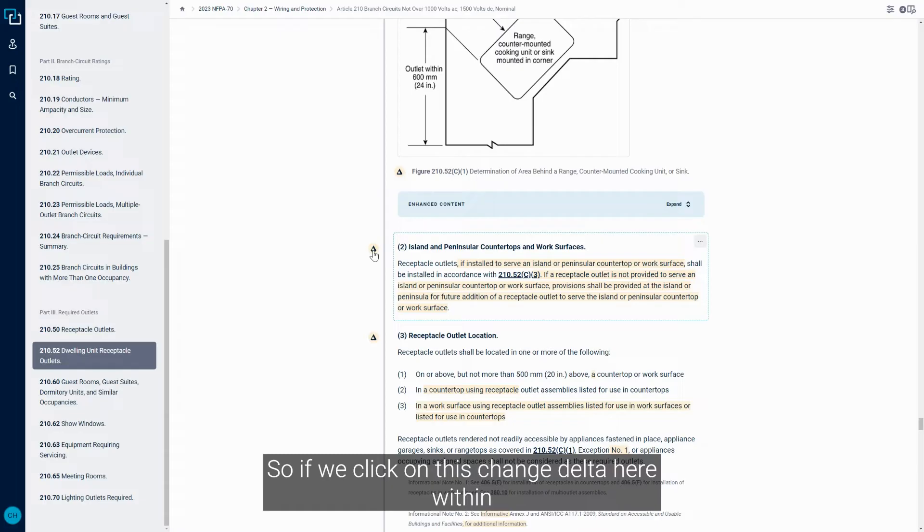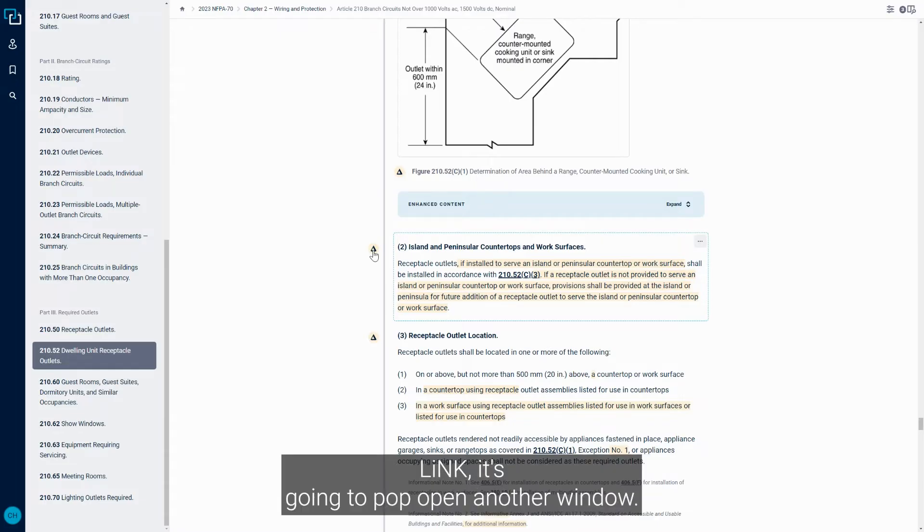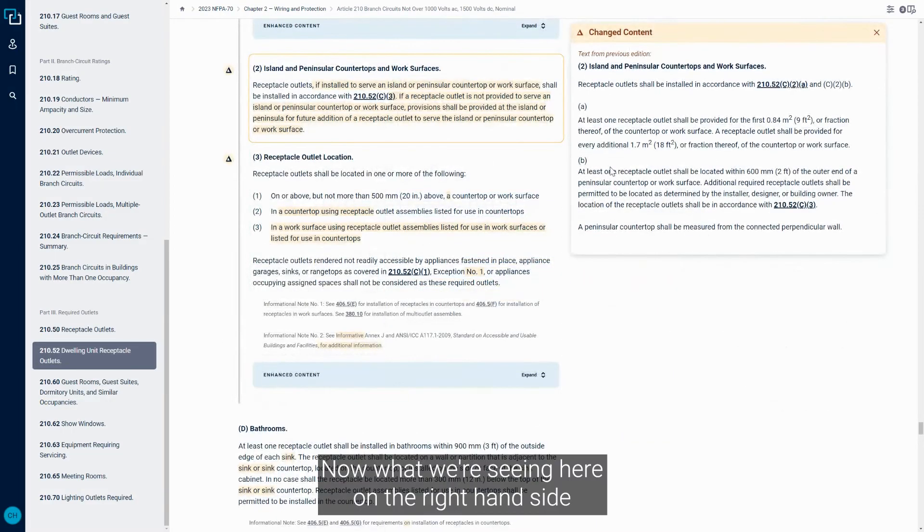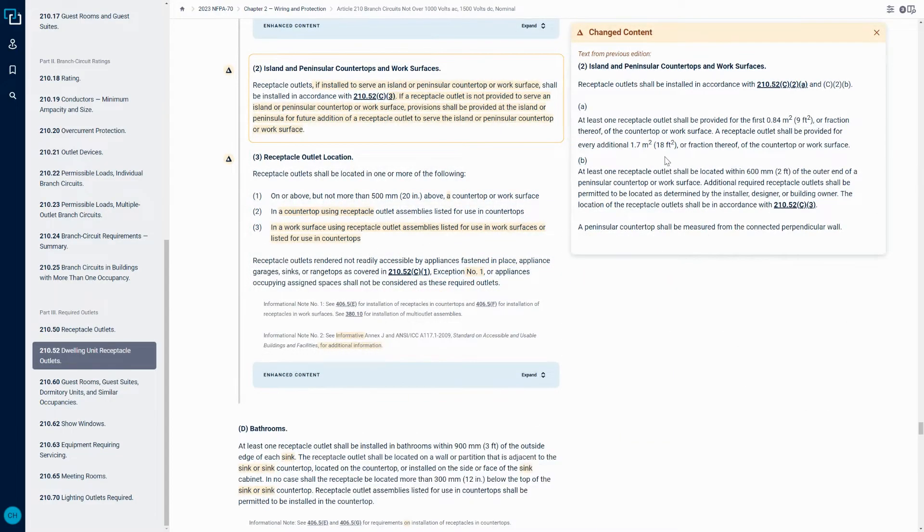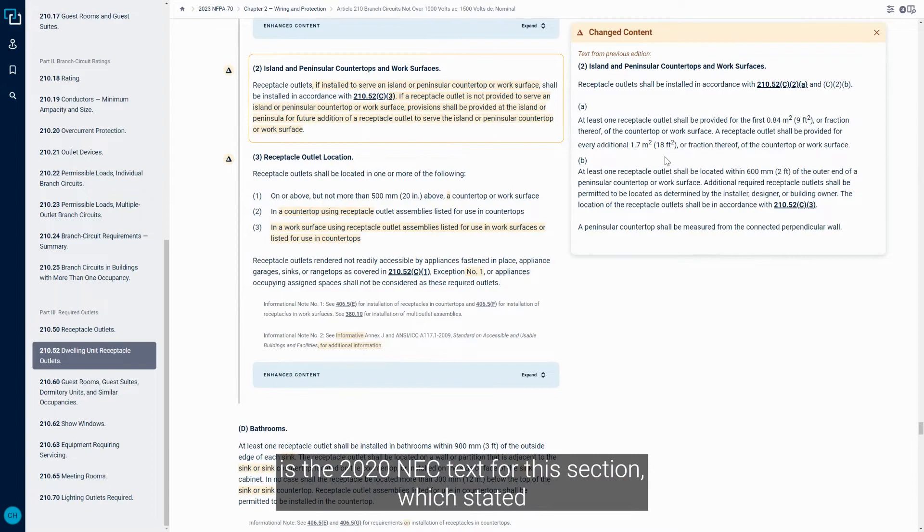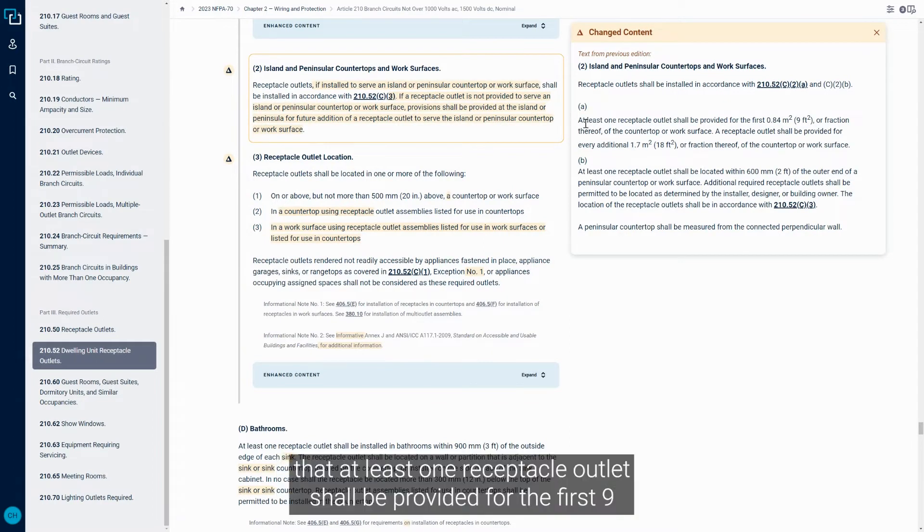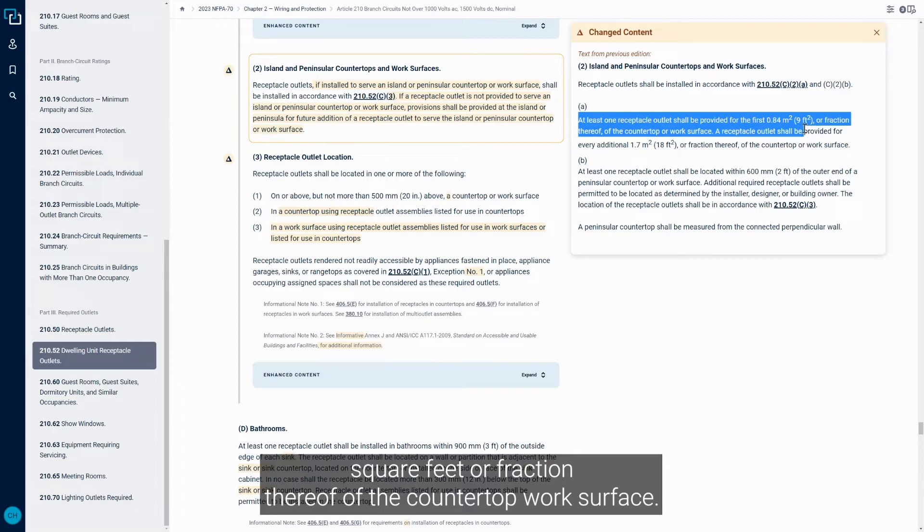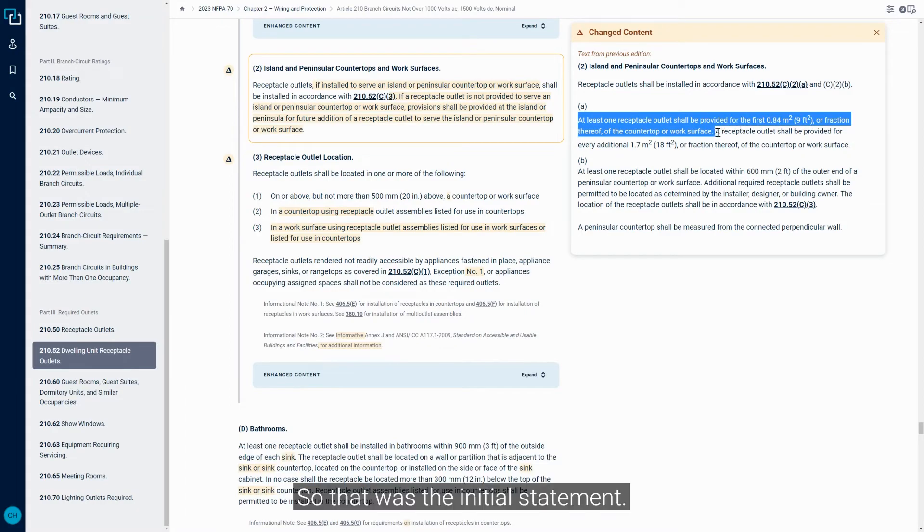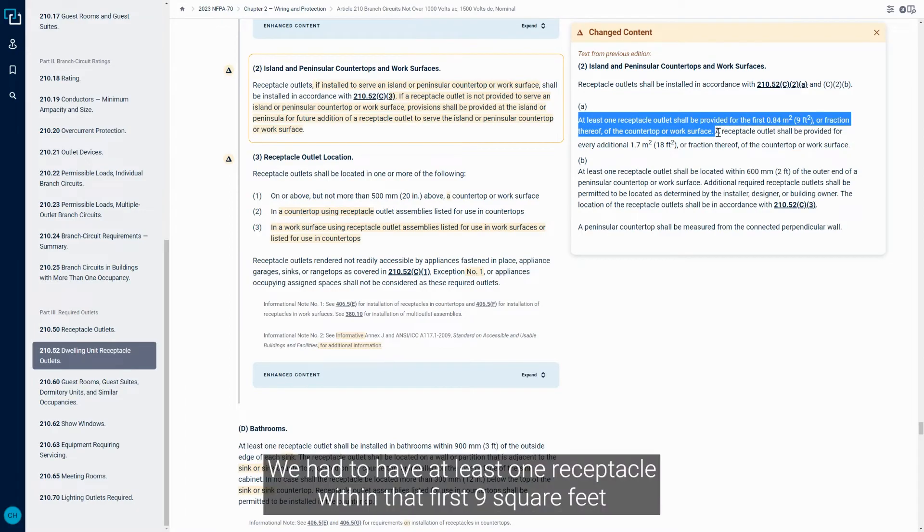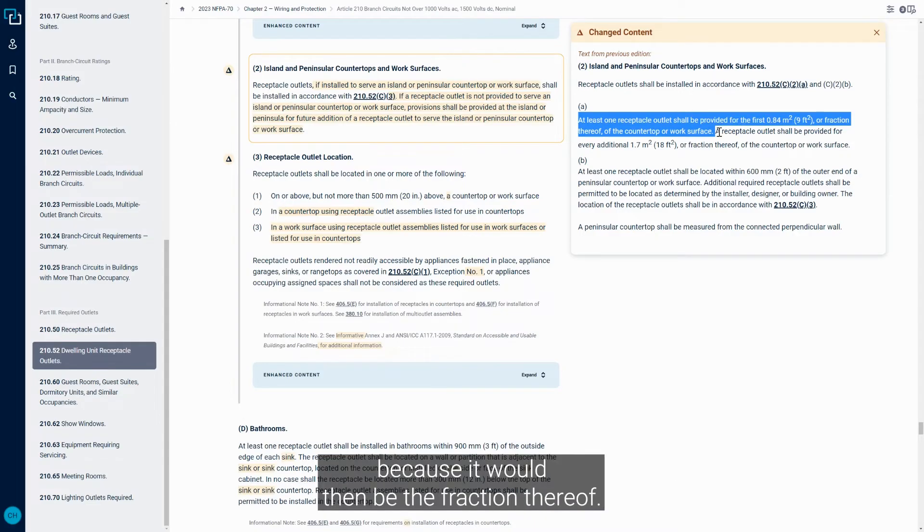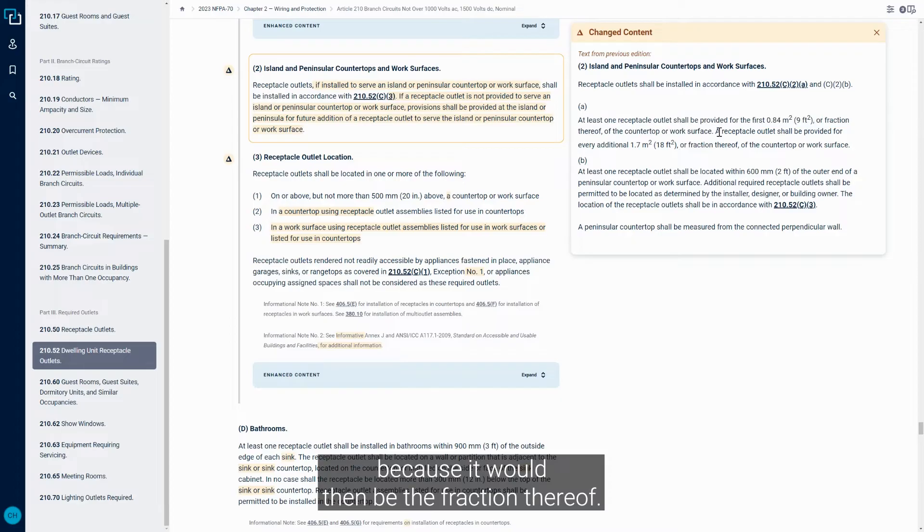So if we click on this Change Delta here within LINK, it's going to pop open another window. Now what we're seeing here on the right hand side is the 2020 NEC text for this section, which stated that at least one Receptacle Outlet shall be provided for the first nine square feet or fraction thereof of the countertop work surface. So that was the initial statement. We had to have at least one Receptacle within that first nine square feet or any less amount of square footage because it would then be the fraction thereof.